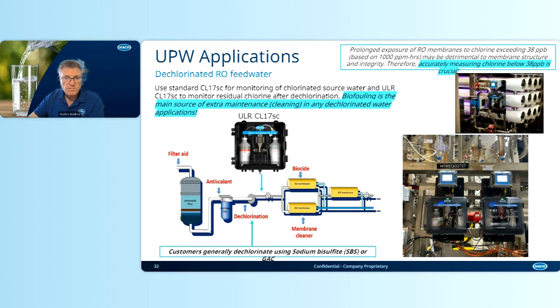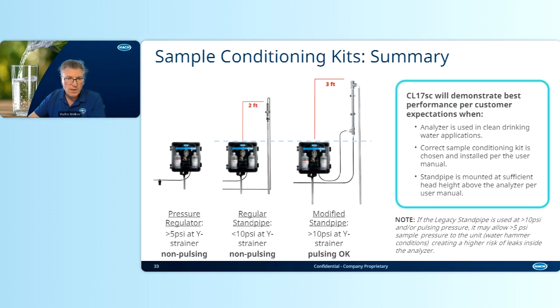All right, from this slide, we're going to jump to the installation. I mentioned that this instrument, the CL17SC, may be more sensitive to the flow and pressure of the incoming sample.